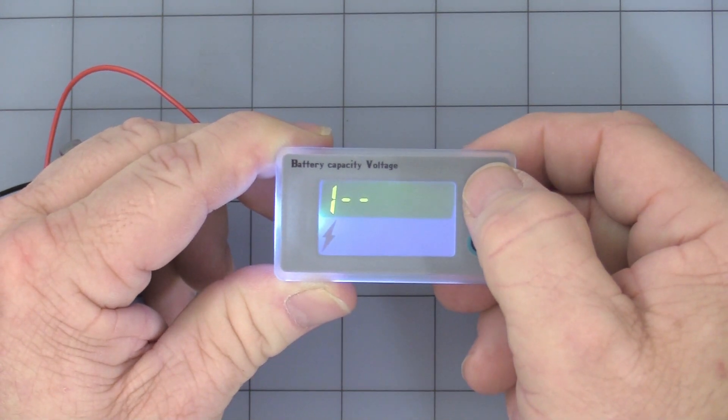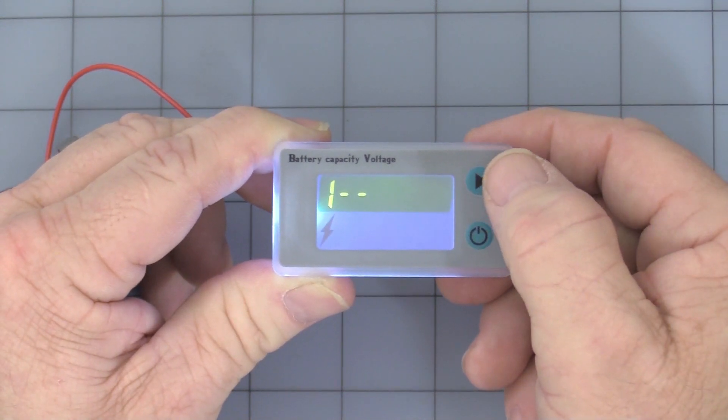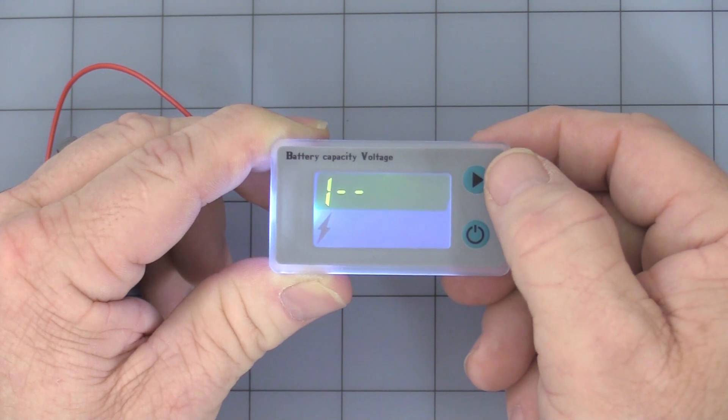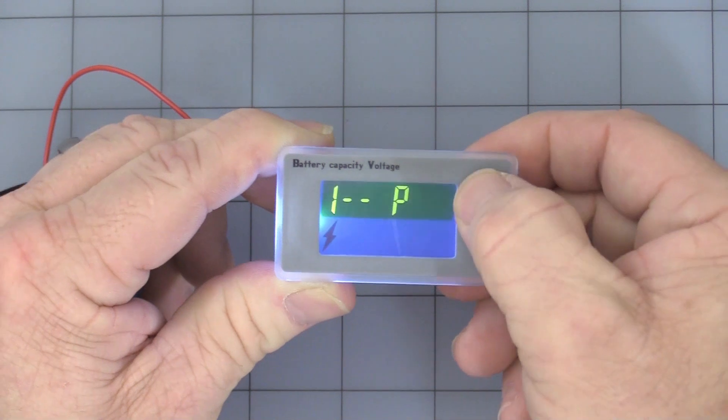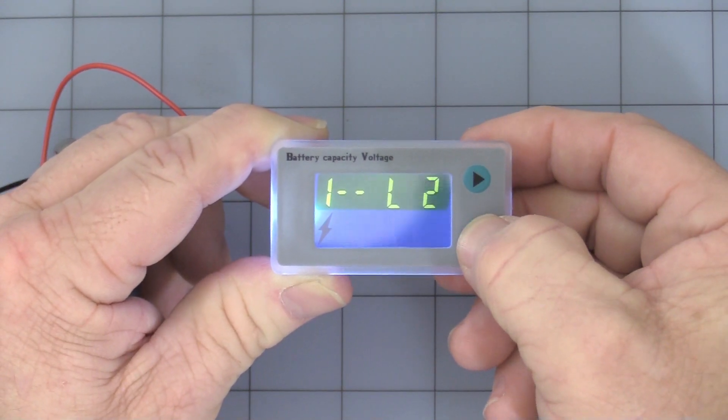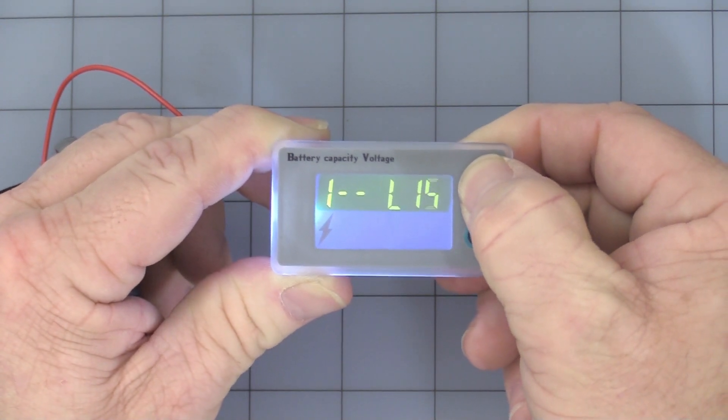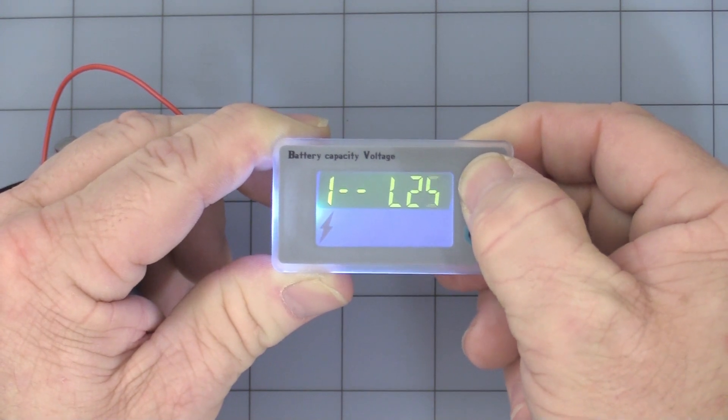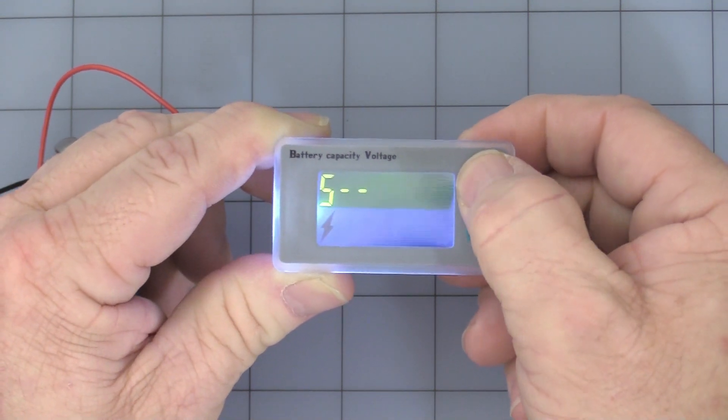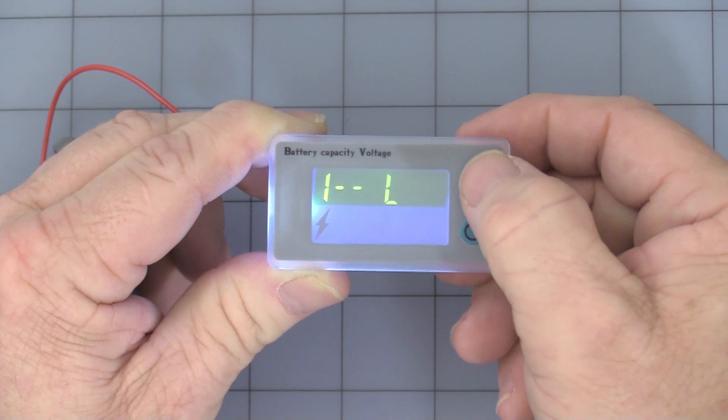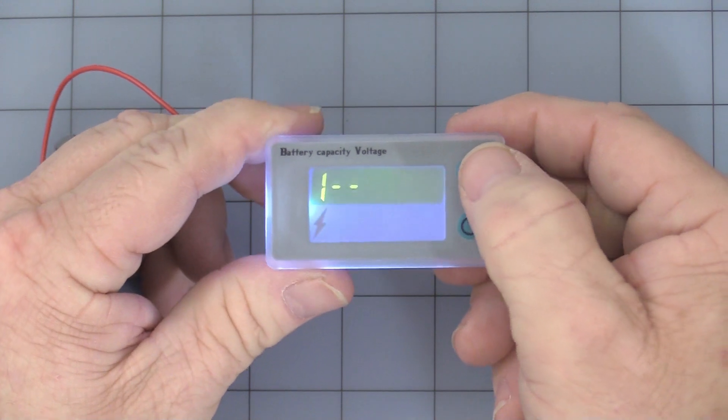That's how you would program what voltage you want your system to use. Press the on off button, it disappears again. It's the same function for both the lithium and lithium iron phosphate battery packs. You can't really use less than four or the voltage is too low. Then you can run up to, let's try it. Lithium, back to one. Lithium. Press the on off, it starts with two cells. That's too low, you can't really use less than four. Lithium ion battery packs, it's good for up to 25 in series. Let's get back to our lead-acid. Okay. That's program one.